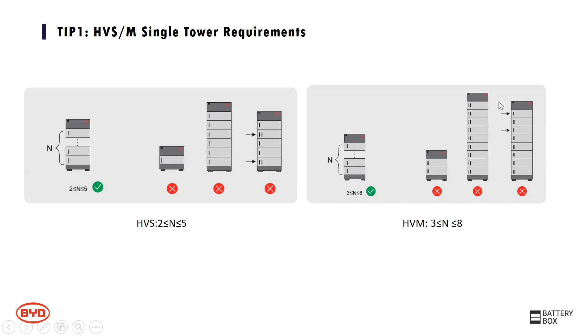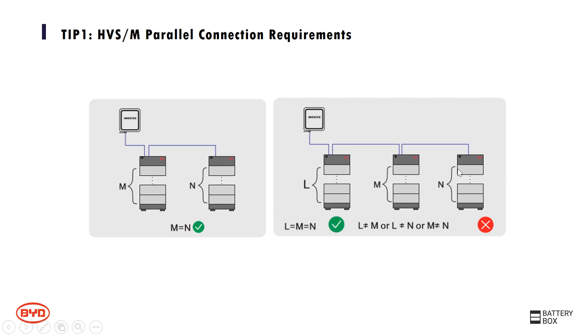For parallel connection, both HVS and HVM support up to 3 towers in parallel. But when you parallel the battery systems, make sure each tower has the same number of modules to get the same voltage. Each tower must have the same voltage for the whole system to work. If the number of modules — L, M, and N — isn't the same across towers, the whole system won't work. I think this makes sense.